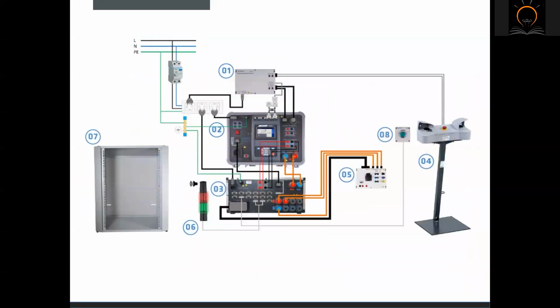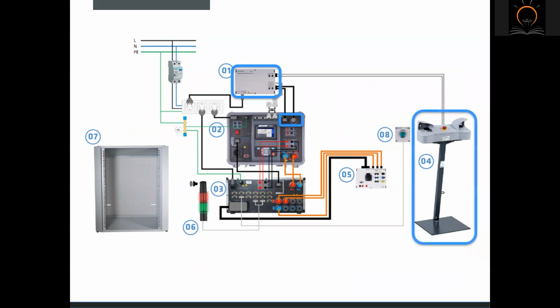The two-hand control module prevents the user from performing hazardous tests. The device only allows the test to start when the user has both hands in contact with the safety set. Both buttons on the pair of hand controls must be pressed during the test. This prevents the user from accidentally coming into contact with the parts that become live during the test.